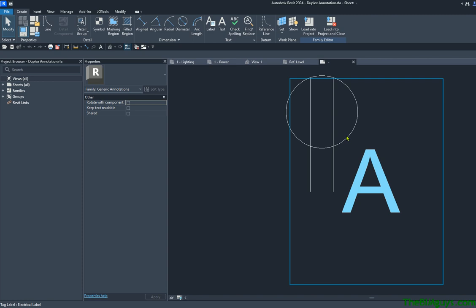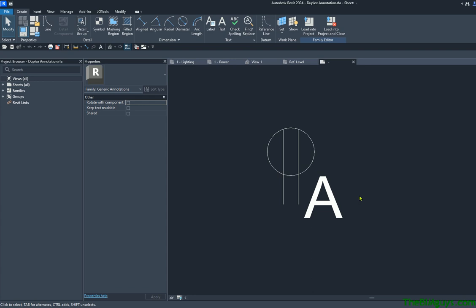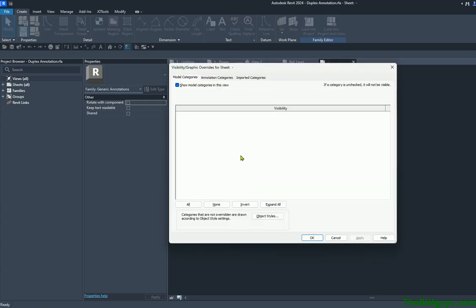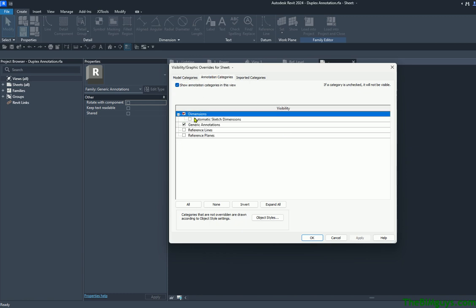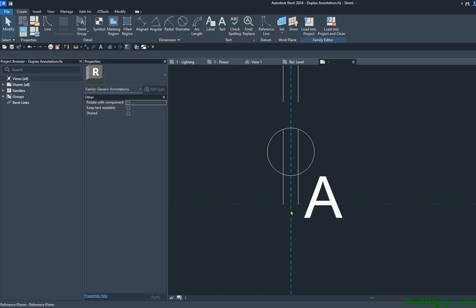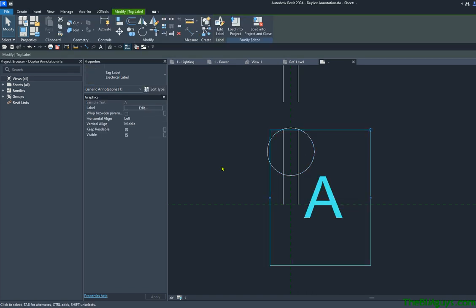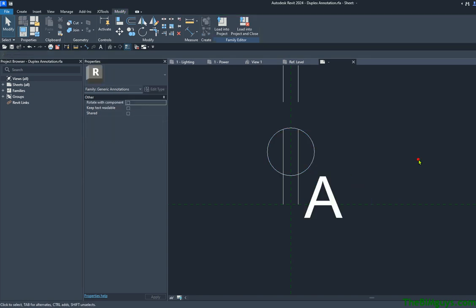The emphasis is on editing this graphic here. The graphic, as it comes up, does not contain any reference planes, so we really don't know where zero is. I'm going to type VV again for Visibility Graphics — don't panic when you don't see anything. Go directly to Annotation because this is an annotative object; it does not contain any physical geometry. Turn on Dimensions and Reference Planes and hit OK — now you can see where zero is. Inside here, you have two pieces: this label, which is built in, lets you type in GFI and different things. The downside of this embedded tag is that it will rotate with the symbol — if the symbol is placed 180 degrees, the text rotates 180 degrees, so you'll see some weird results. Some people will take this out and just use tags, but that's beyond the scope of this video.